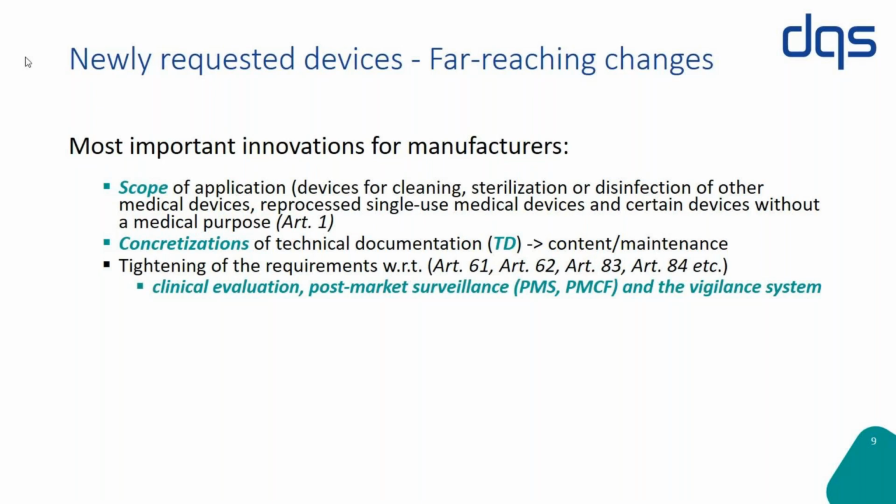For example, in former times under the old directive, we often had just one auditor who took a closer look at the clinical evaluation, made a kind of update in his technical file review, and everything was fine. Nowadays, we need extra clinical experts to take a look at the clinical evaluation to perform something called a clinical evaluation assessment report. So we have nowadays more instances to take a look at this data, as well as more instances to take a look at the surveillance activities.